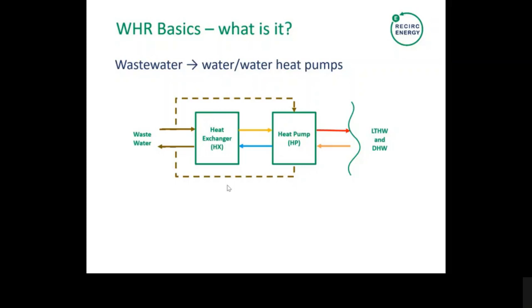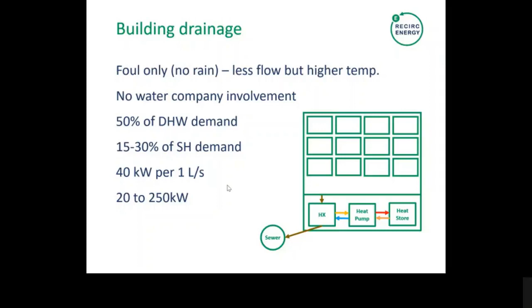One of the first things I'd like to point out, and this has been done mainly in North America, is that it is possible to take the wastewater from a building itself, particularly if it's large enough, so it's producing a significant amount of water, and we can extract the heat from that. It's nice and warm as it's come straight from the building and not from the sewer in the ground, and it is possible in most cases to recover around 50% of the domestic hot water demand just from what the building produces itself. Obviously a much smaller fraction of the space heating demand. A couple of little rules of thumb there: you could get somewhere akin to 40 kilowatts of heat production out of 1 litre per second using that technology, and the systems can range anywhere from 20 to 250 kilowatts or even higher. Here's a couple of examples of the technology.